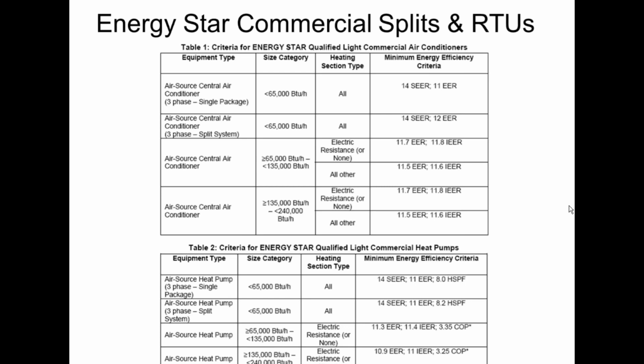So here's the specs: air conditioner on top, heat pumps on the bottom. So for small stuff, 5 tons and under, you have to be 14 SEER. And then you have to have 11 EER if you are a packaged rooftop style unit, 14 SEER, 12 EER if you are a split system style unit. So you have to meet both the part load and the full load efficiency.